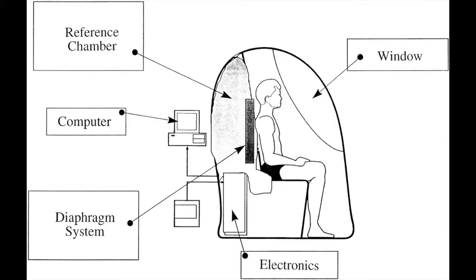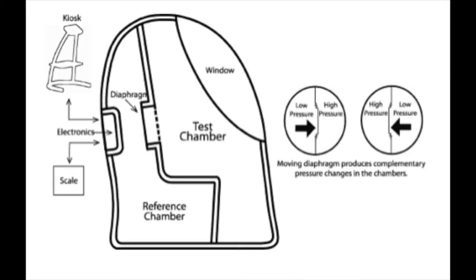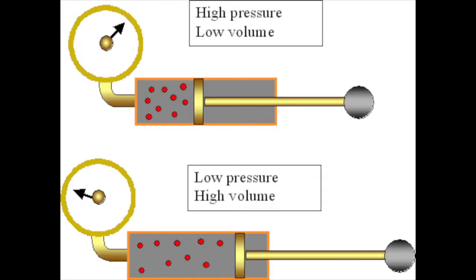The Bod Pod measurement process begins with a baseline measurement of the pressure and volume of the empty test chamber. The Bod Pod consists of two chambers, the test chamber and the reference chamber, with a common wall between the two. In the wall between the two chambers, there's a diaphragm that oscillates during testing to produce small changes in the volume to the test and reference chambers. When the volume increases in one chamber, it decreases equally in the other. The pressure in the two chambers responds immediately to these changes in volume, and the degree to which the pressure changes indicates the size of each chamber.